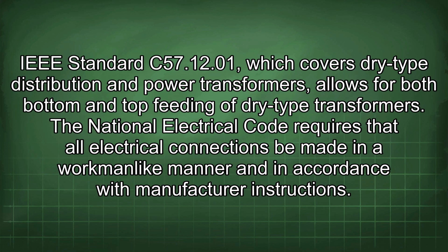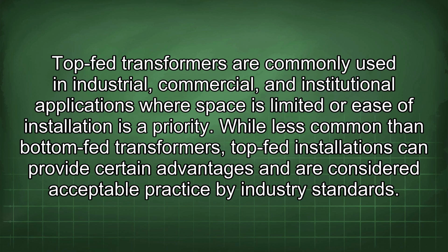IEEE Standard C57.12.01, which covers dry-type distribution and power transformers, allows for both bottom and top feeding of dry-type transformers. The National Electrical Code requires that all electrical connections be made in a workmanlike manner and in accordance with manufacturer instructions. Top-fed transformers are commonly used in industrial, commercial, and institutional applications where space is limited or ease of installation is a priority. While less common than bottom-fed transformers, top-fed installations can provide certain advantages and are considered acceptable practice by industry standards.